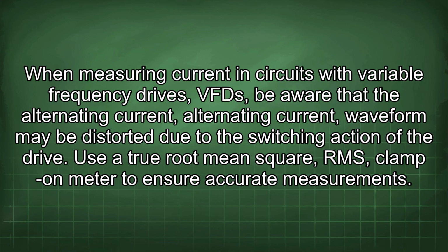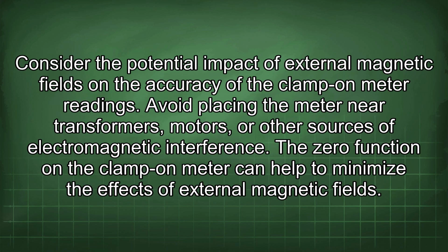Use a true root mean square RMS clamp-on meter to ensure accurate measurements. Consider the potential impact of external magnetic fields on the accuracy of the clamp-on meter readings. Avoid placing the meter near transformers, motors, or other sources of electromagnetic interference. The zero function on the clamp-on meter can help to minimize the effects of external magnetic fields.